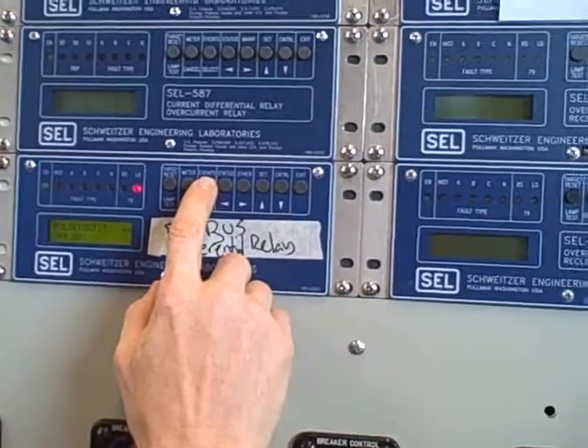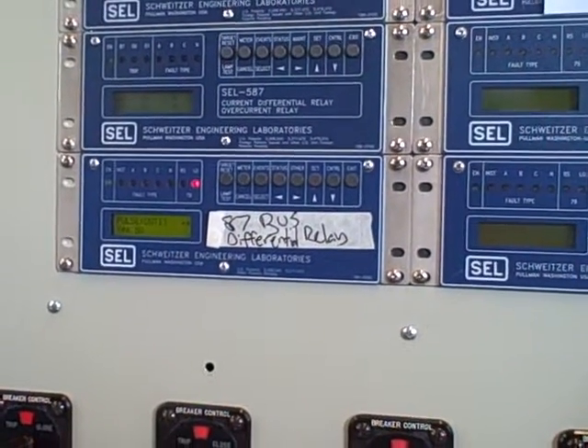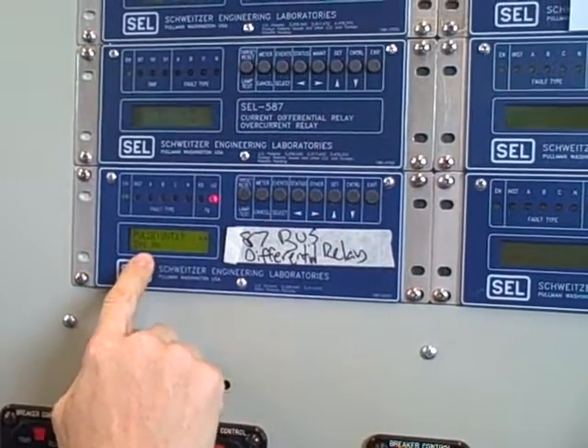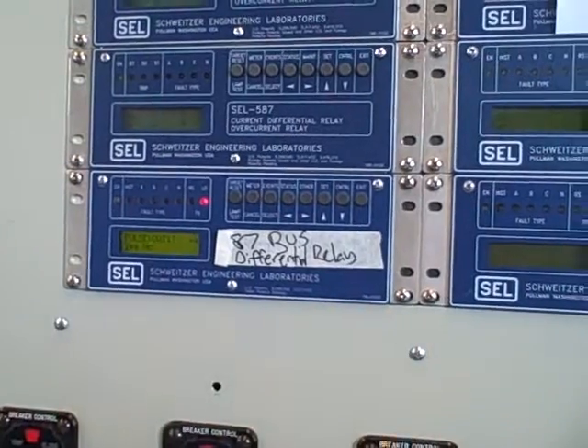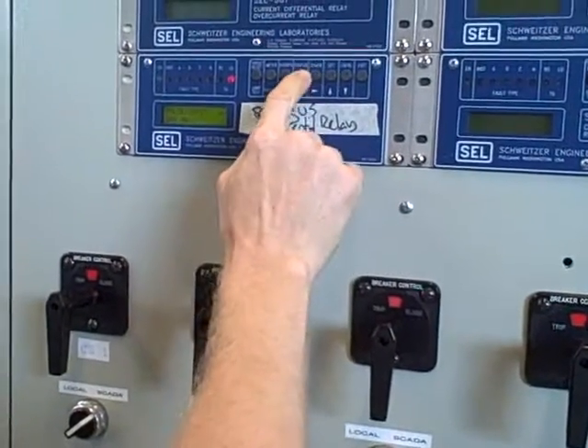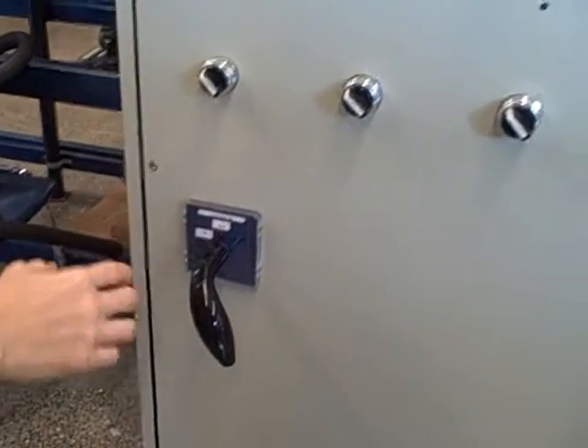I'll select that. It says do you really want to do this — which is a good thing, because you really want to think twice before doing this in a working system. By pulsing this output contact I'm essentially forcing a trip condition. After I move the toggle over to the yes mark I press select, and there we go. It pulsed the output — that tripped my lockout relay, the spring-loaded handle kicked over to the trip position, and that tripped all my breakers.